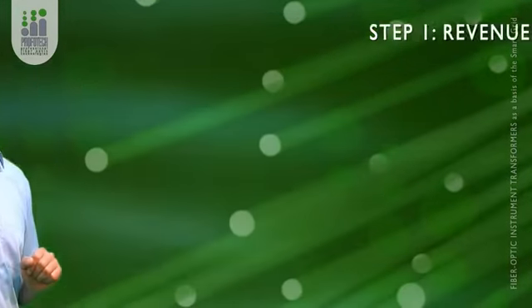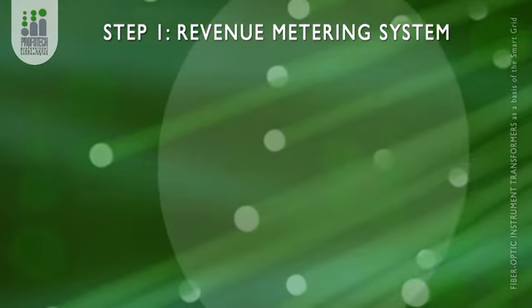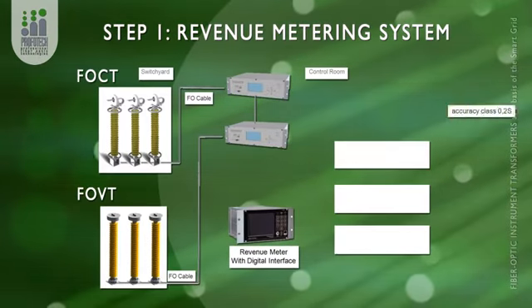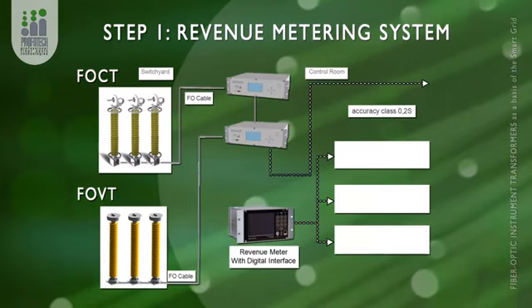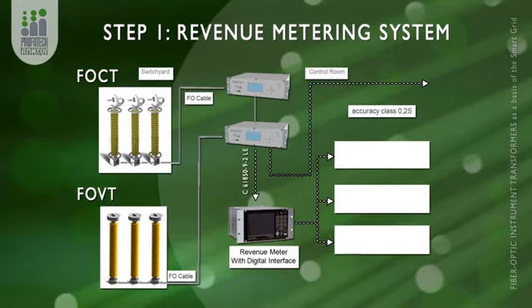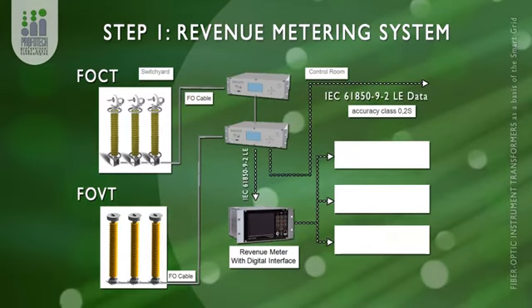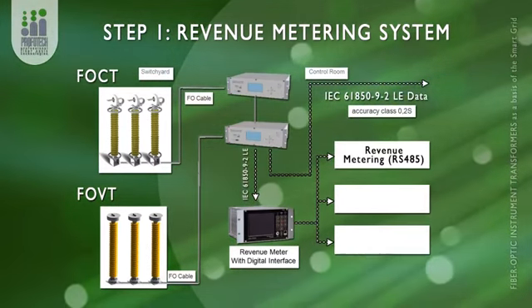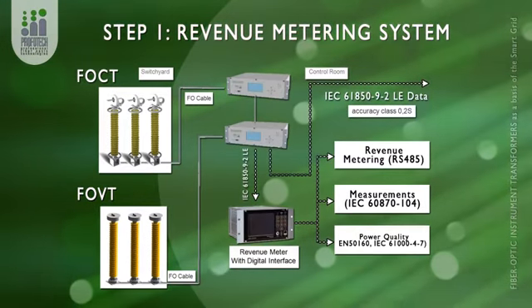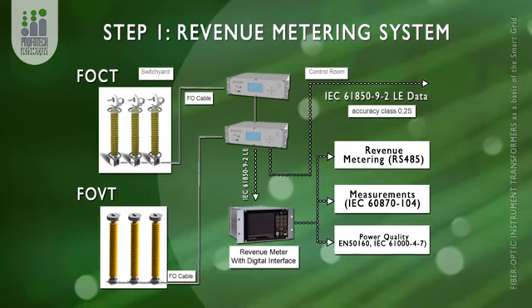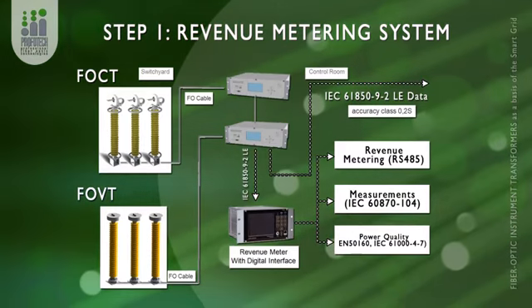We are not proposing to start a revolution in the industry, but we are proposing the opportunity to convert to digital substations with a practical step-by-step process. The first step is a revenue metering system. The new equipment being installed would be parallel to the existing conventional instrument transformers. For this, we don't need much space for installations, as they can be installed near the existing transformers.